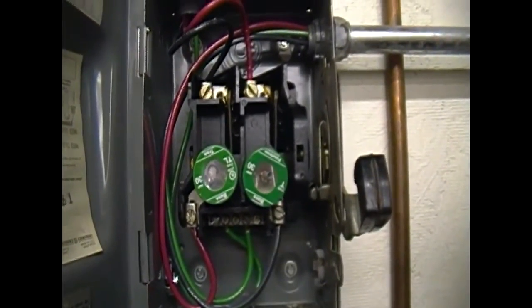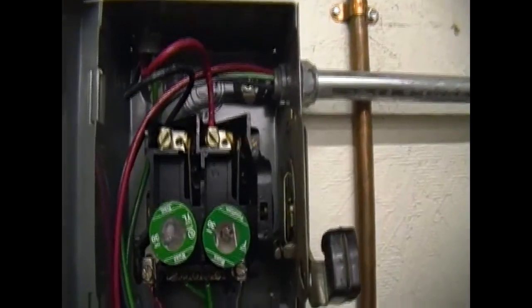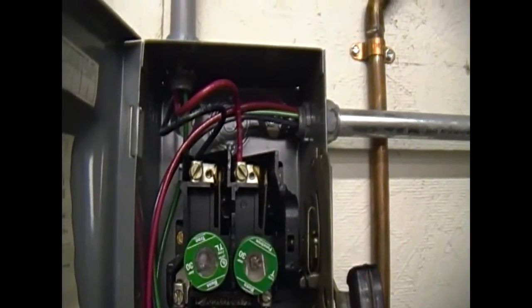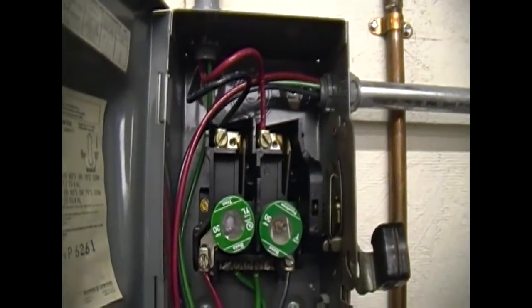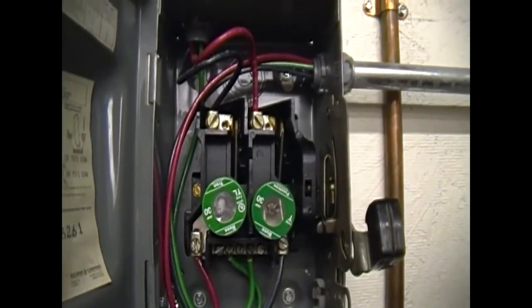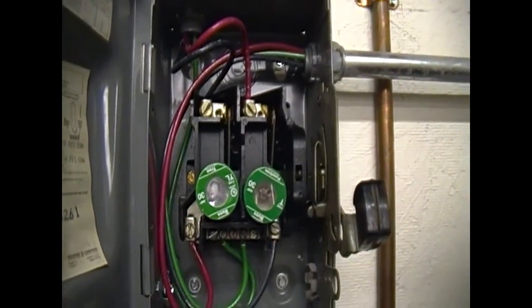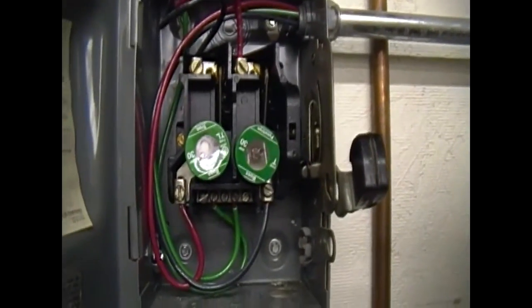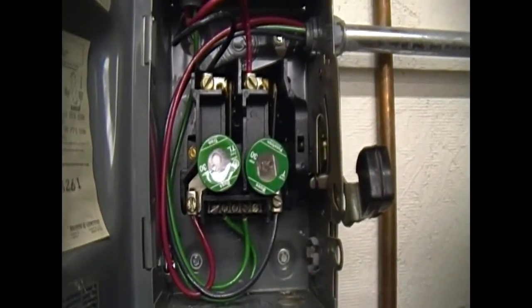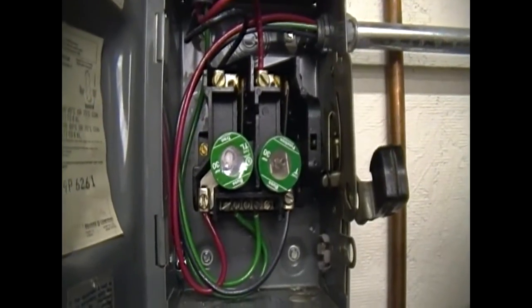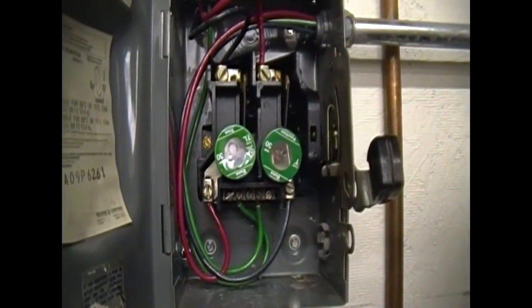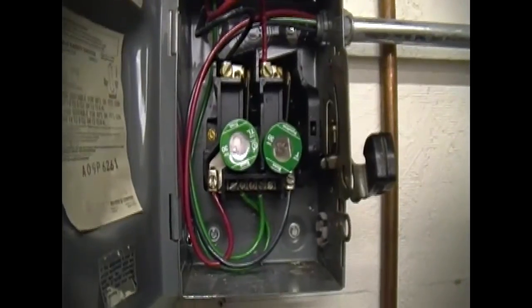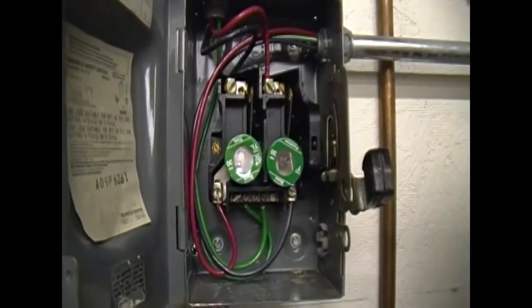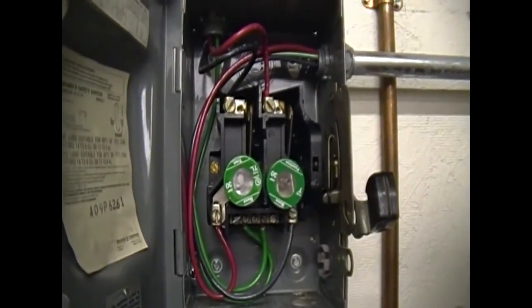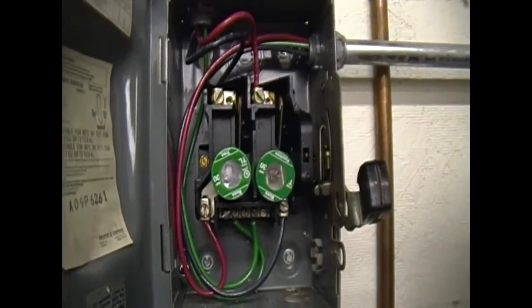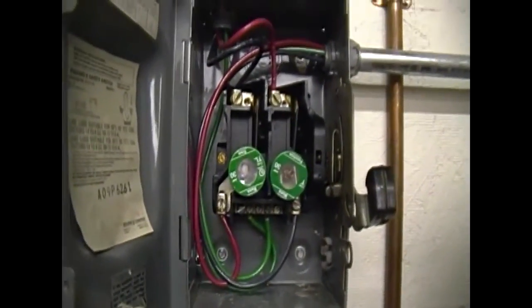Last time this happened, I actually checked my voltage, and the voltage was right where it was supposed to be. Each leg was about 122 to 123 volts, and it was consistent to the contactor on the motor as well. So I suspect, like I said, either there's a loose connection on that leg, or it's a bad circuit breaker, so it's always the same leg. So evidently the compressor tried to start when I was not in the shop here, and never got off, because I see that the tank is down to 60 psi. So we're going to replace this fuse and give it another shot.